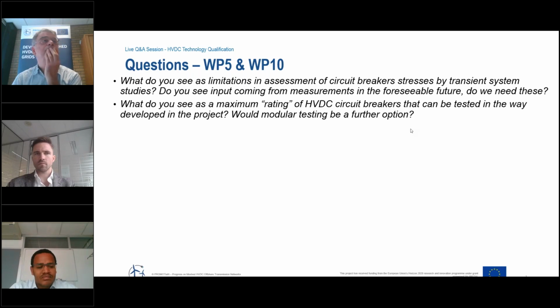That means you need to have the rated voltage and rated short circuit current from your supply, and that also translates to energy later. So you have to be able to supply all those stresses to the circuit breakers. The second challenge is coming from the breaker itself. That means your test environment, the whole installation, must be able to deal with the stress that is coming from HVDC circuit breakers, which is unique because most laboratories are not built for testing HVDC circuit breakers.